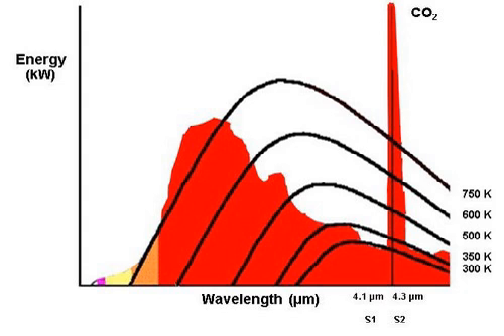Infrared. Infrared (IR) or wideband infrared, 1.1 micrometers and higher, flame detectors monitor the infrared spectral band for specific patterns given off by hot gases. These are sensed using a specialized fire-fighting thermal imaging camera (TIC), a type of thermographic camera. False alarms can be caused by other hot surfaces and background thermal radiation in the area. Water on the detector's lens will greatly reduce the accuracy of the detector, as will exposure to direct sunlight.